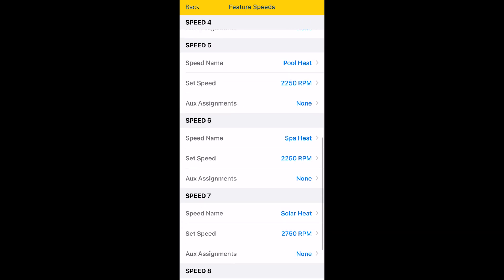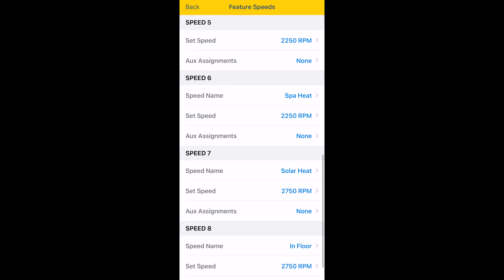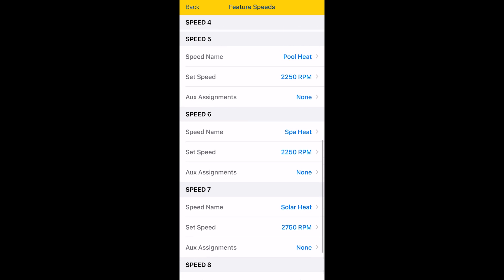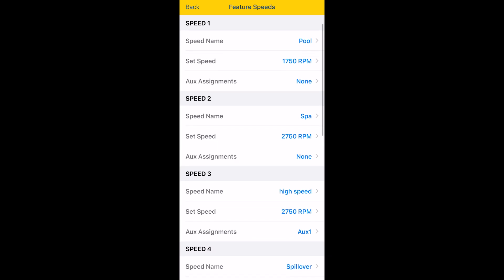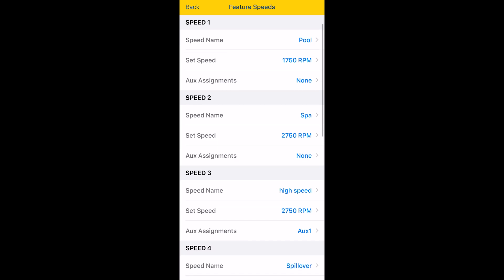Their default numbers are relatively accurate. You don't want to run the water through the heater too fast or too slow, especially in the wintertime. If you run it too fast, you'll actually cause condensation, which will prematurely soot the heater up. So 2250 translates to about 50 to 60 gallons a minute, which would be ideal in the wintertime.